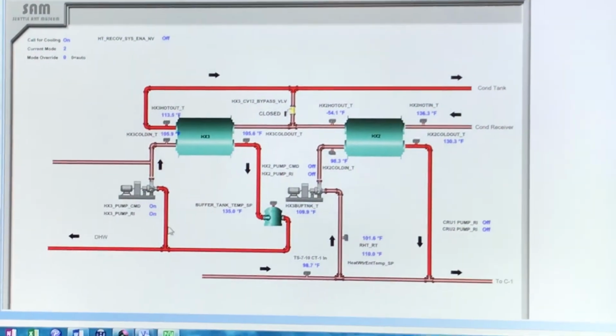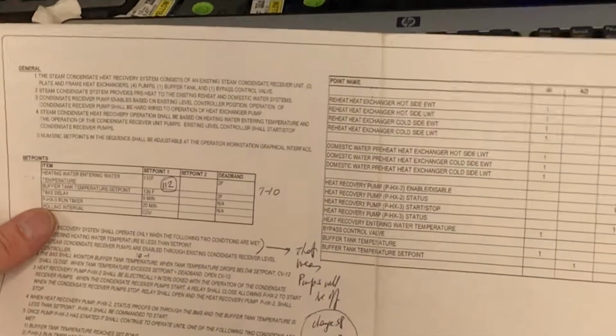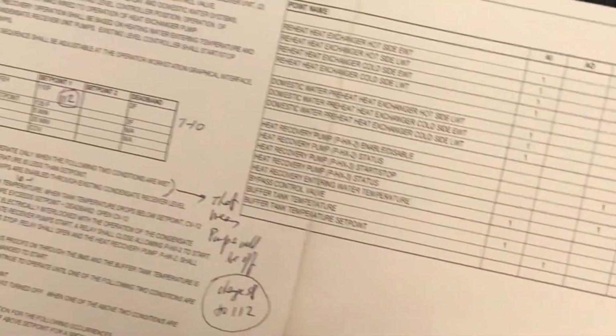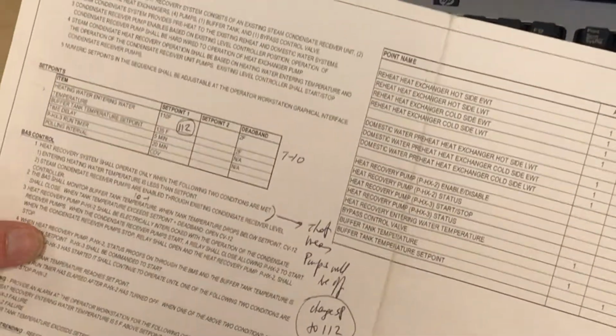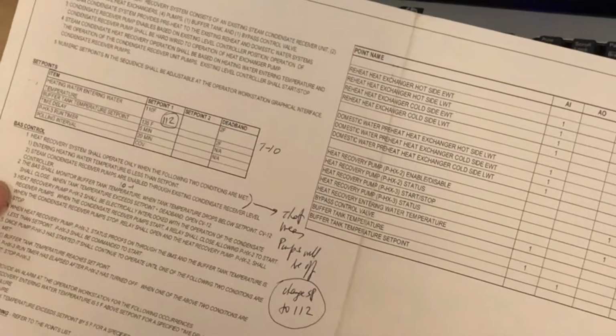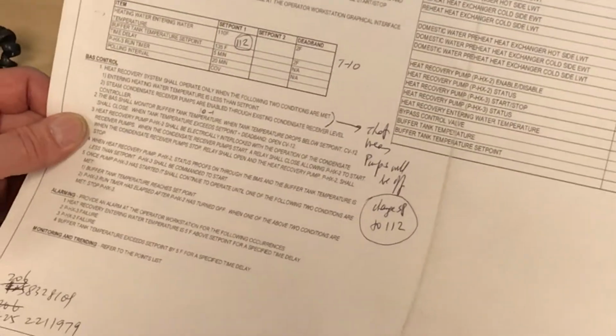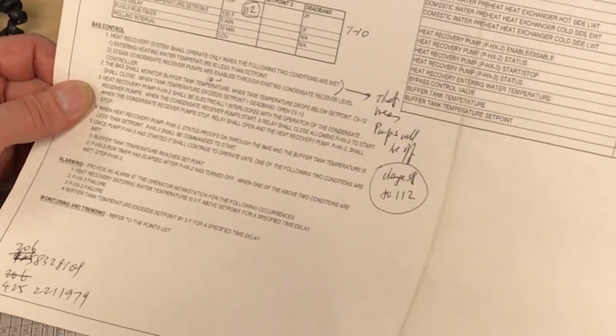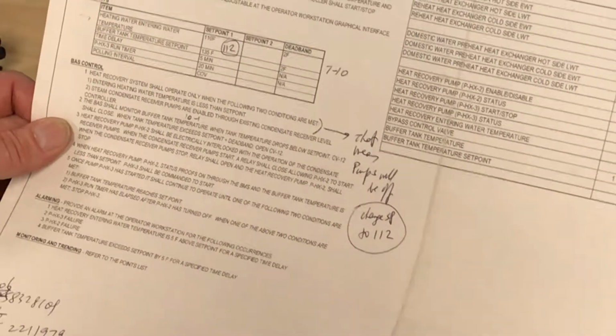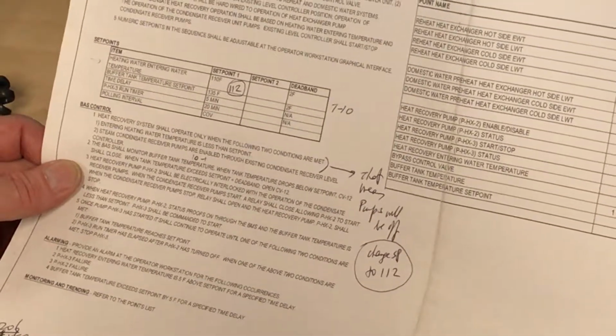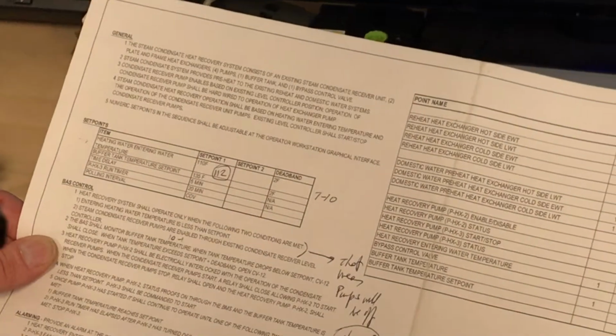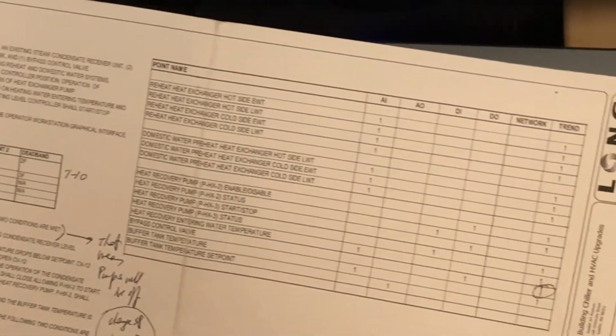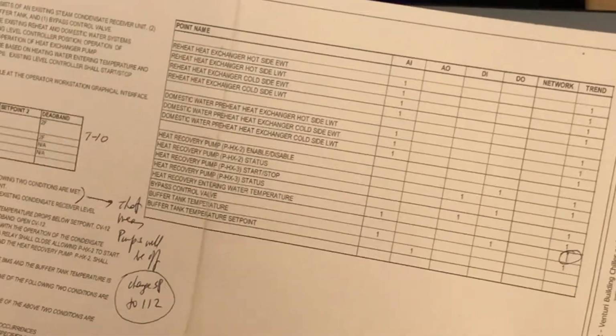Here's the sequence. So, pumps 2 and 3: one is the condenser, one is the evaporator, right? That's for those. This is for the hot water system. Yeah, that's for the domestic hot water, but it's tied to the heat recovery loop also, because you're using the condenser water from the heat recovery. I think what they're trying to do here is recover some of the heat from the steam condensate. Normally the steam condensate goes through a smaller heat exchanger where you use cold water to cool it down before you dump it into the drain.